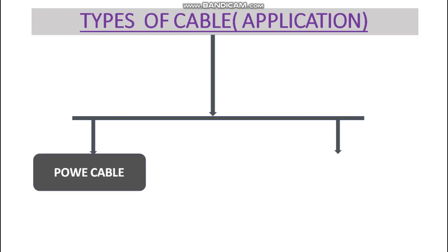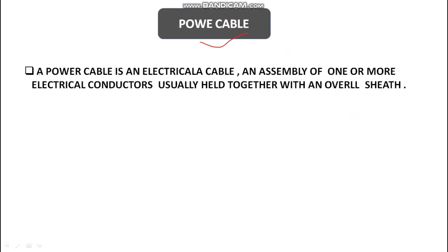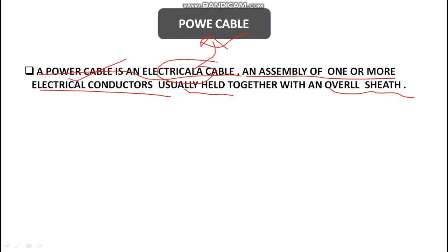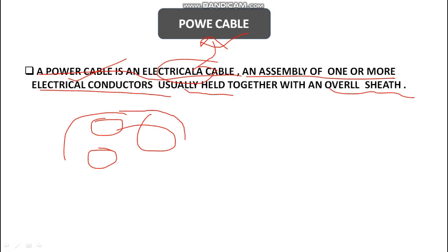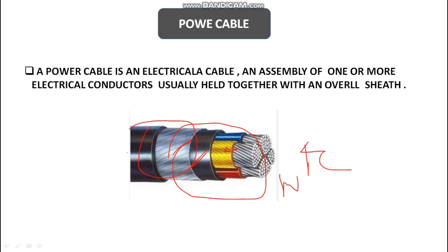Now let's come to the types of cable as per the application. There are two types: power cable and control cable. A power cable is an electrical cable — an assembly of one or more electrical conductors, usually held together with an overall sheath providing mechanical protection. As you can see, this is a four-core power cable with R, Y, B, and one neutral. Over it we have insulation, then the armor which gives mechanical protection, and again an overall sheath which can be PVC or XLPE.